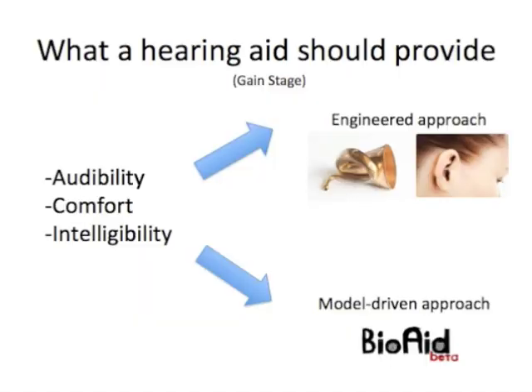I've written in brackets 'at the gain stage', because that's what this talk is really focused on. Modern hearing aids provide all kinds of processing functionality in terms of microphone arrays, beamforming, and noise reduction techniques, but I'm going to focus in on the gain stage. What it needs to do is provide audibility of sounds that would otherwise be inaudible to a hearing-impaired listener. Hearing-impaired listeners generally have a raised threshold of hearing, so they need some kind of gain boost. However, normal and impaired listeners tend to have a similar maximum level at which they can tolerate sounds.